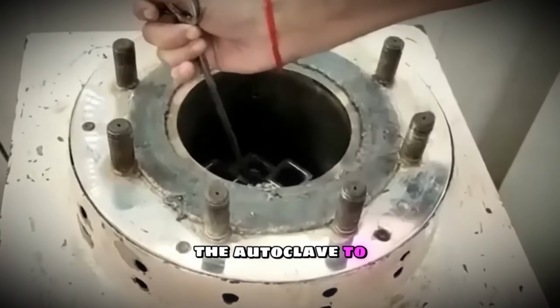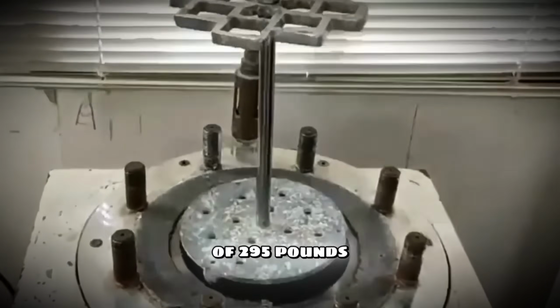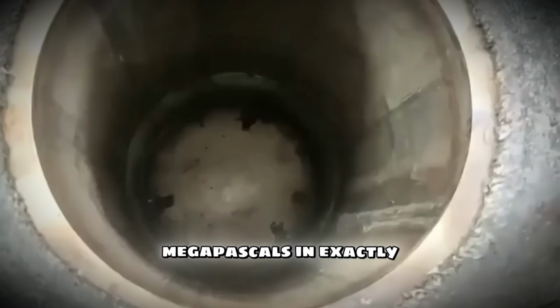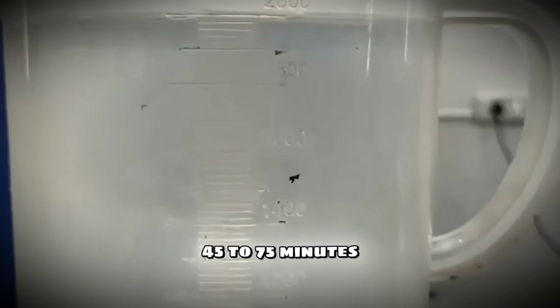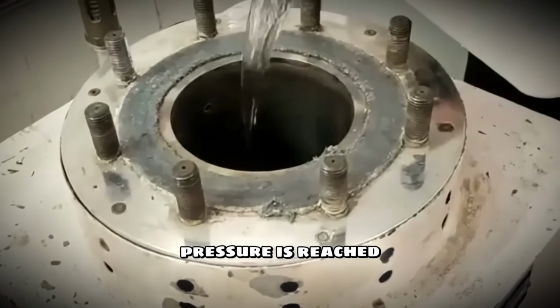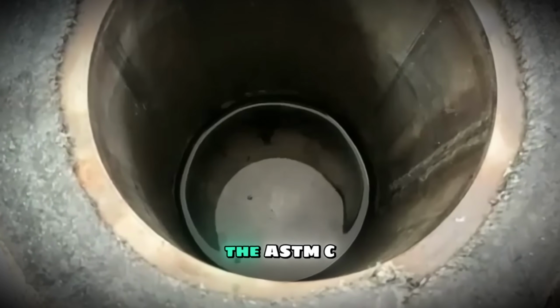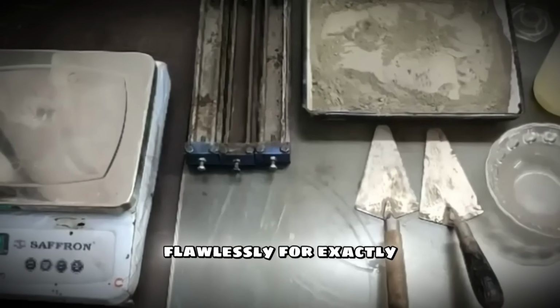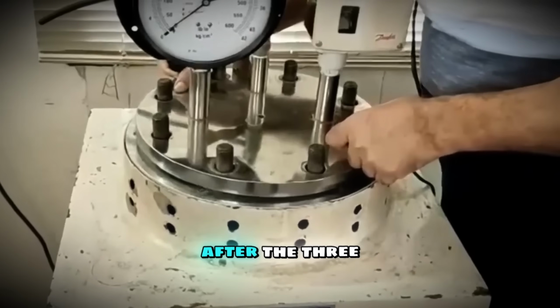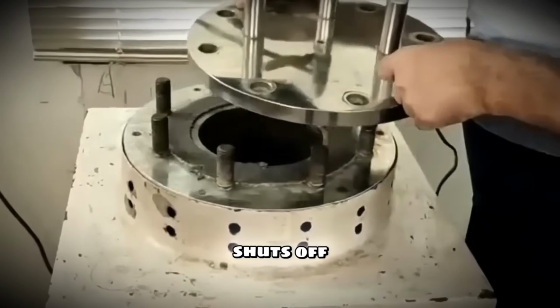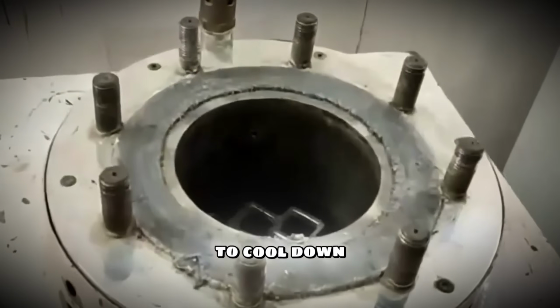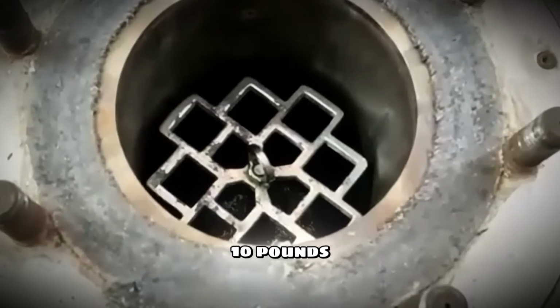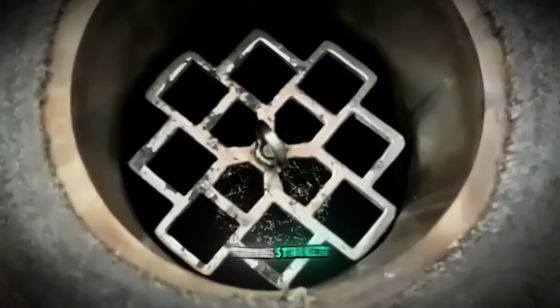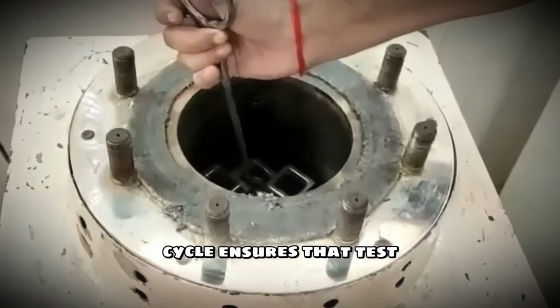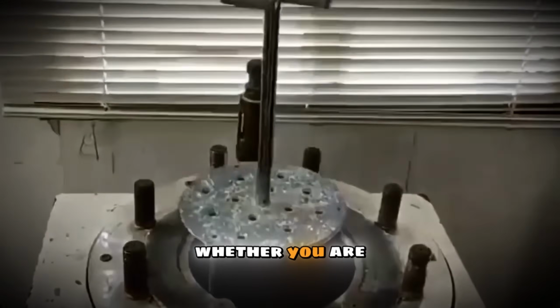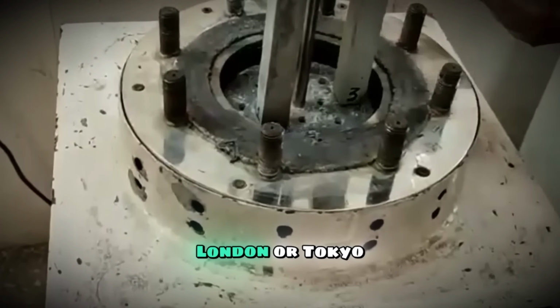The standard requires the autoclave to reach a pressure of 295 pounds per square inch, or about 2 megapascals, in exactly 45 to 75 minutes. Once that massive pressure is reached, the ASTM-C151 autoclave must maintain it flawlessly for exactly 3 hours. After the 3-hour hold, the heating element shuts off, and the autoclave must be able to cool down so that the pressure drops back to less than 10 pounds per square inch within an hour and a half. This strict thermal and pressure cycle ensures that test results are uniform and reproducible, whether you are testing cement in New York, London, or Tokyo.